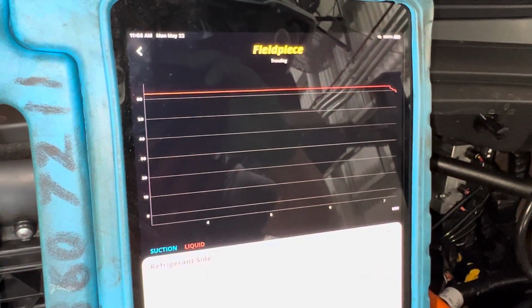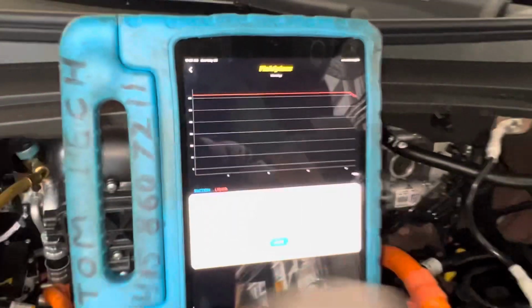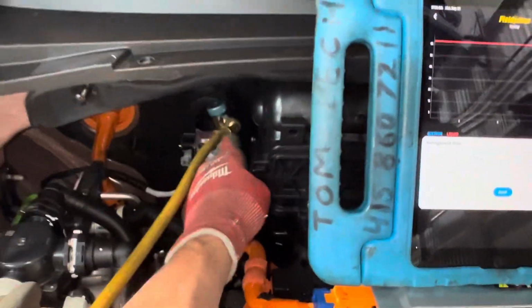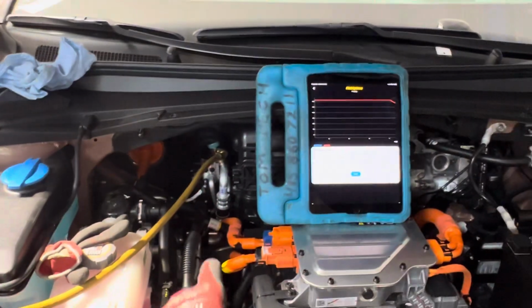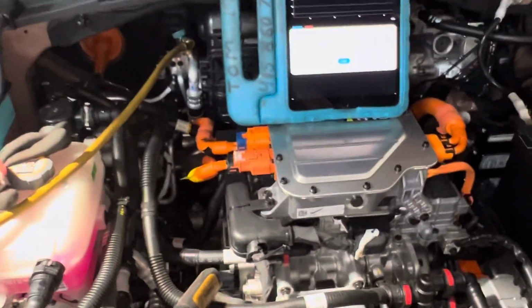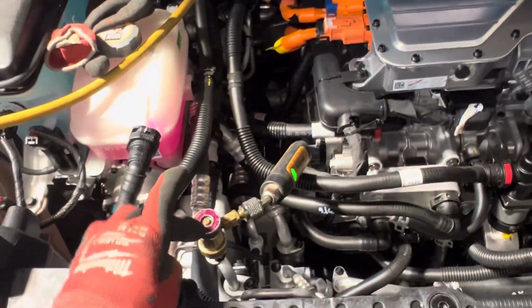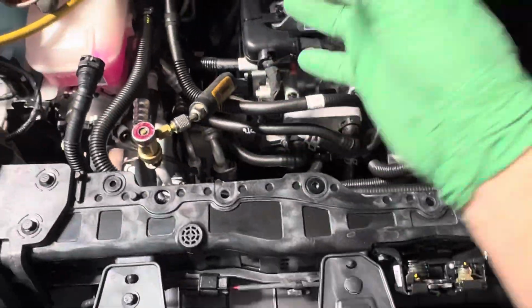Focus, there you go. So we're sucking the refrigerant out from the suction line on the low side, and we're trying to see if we get any trapped refrigerant in the system by monitoring the high side. I'm trying to see if shutoff valves actually trap refrigerant in this system.